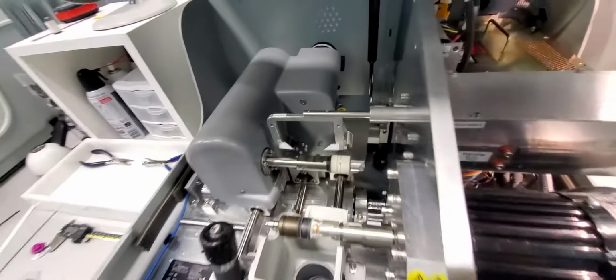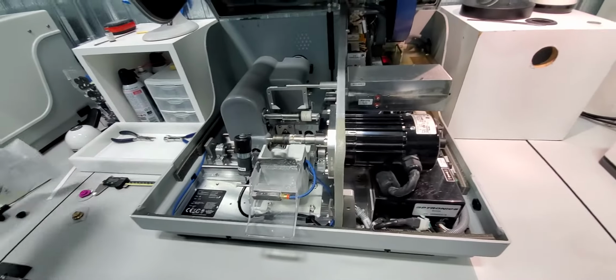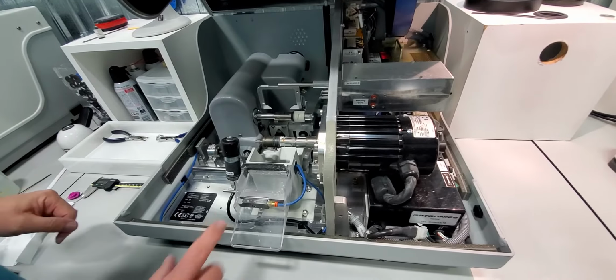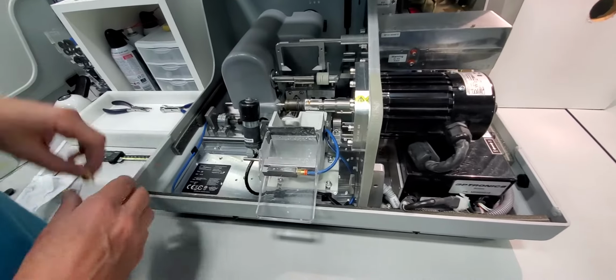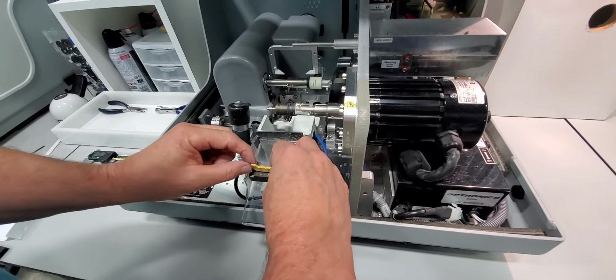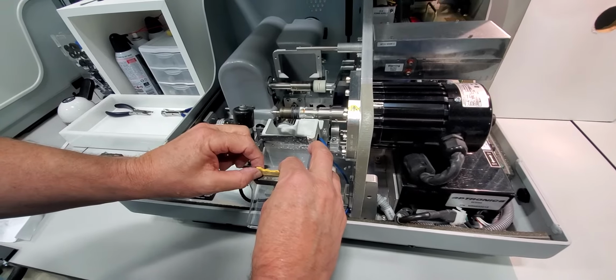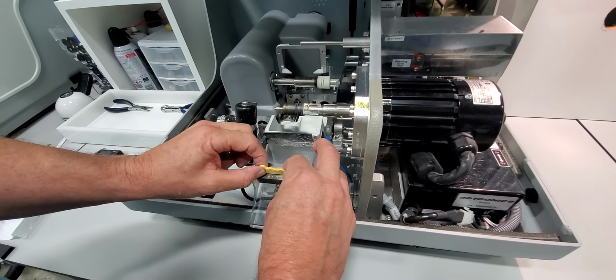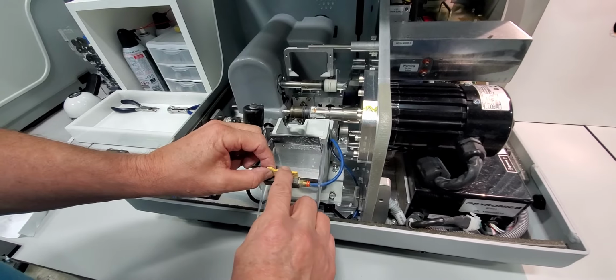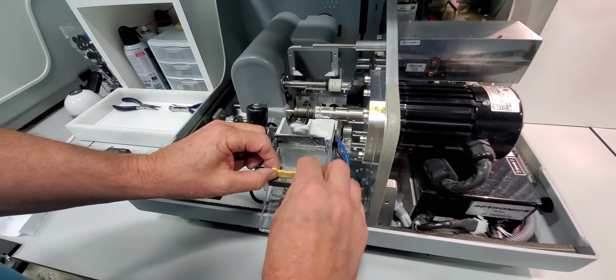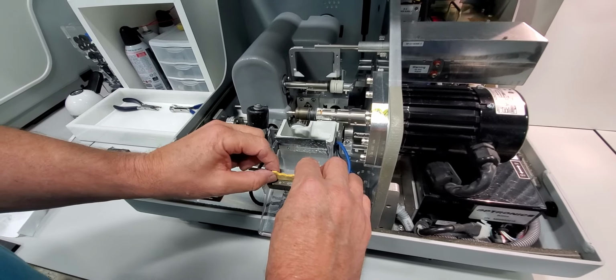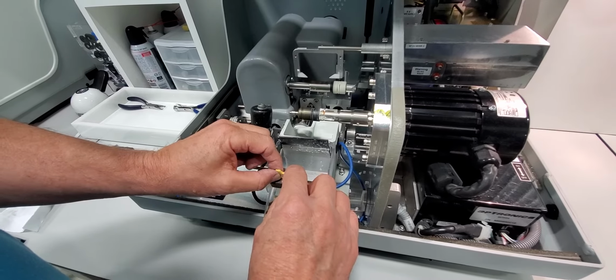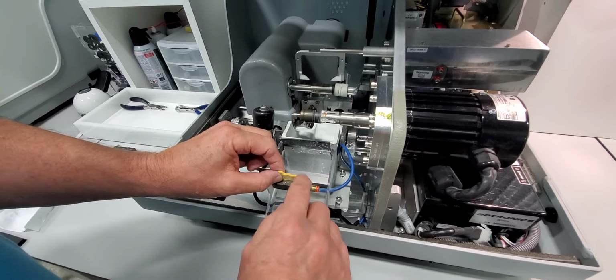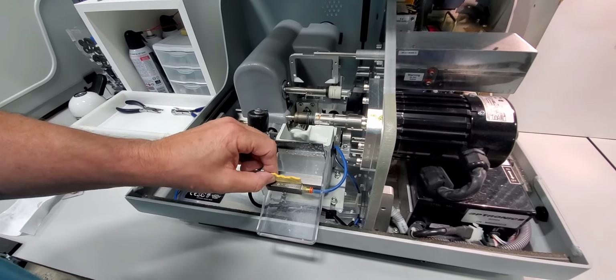Perfect. And then also, Mike, can you show us how you would inspect the sponge? The sponge goes right there. Be right in here like this. Of course, it would be fanned out because it would be wet. And you want to check to make sure that there's nothing missing, no chunks out of it. Might be very dirty. The dirtier it gets, the worse it's going to be for the lens. So you might want to replace it if it's dirty or worn.